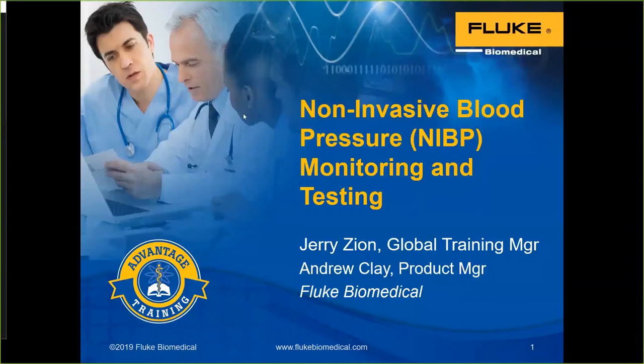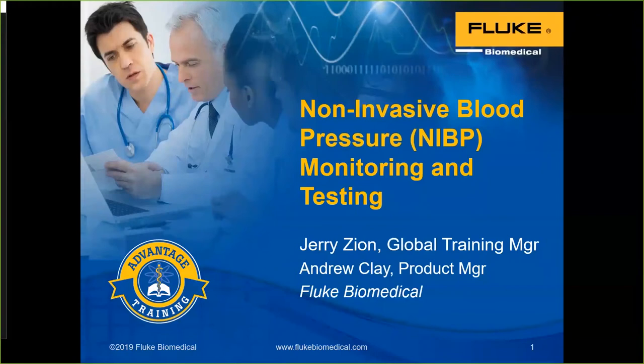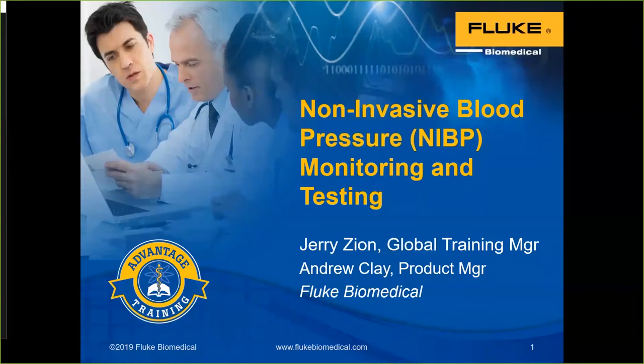Today we're going to talk about doing testing on non-invasive blood pressure monitors. There are some things I learned while I've been here at Fluke Biomedical, about 15 years or so, that I didn't know when I was doing what you're doing. We want to share that information so you're doing the testing on non-invasive blood pressure correctly — specifically around understanding the difference between measuring for accuracy per specifications and doing a dynamic simulation.